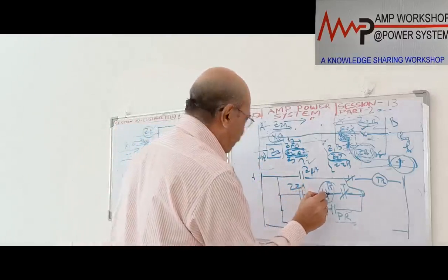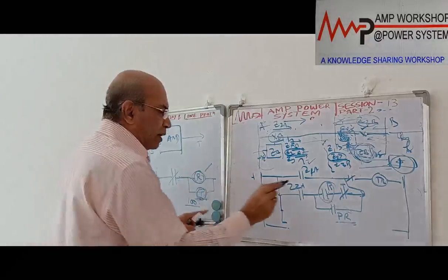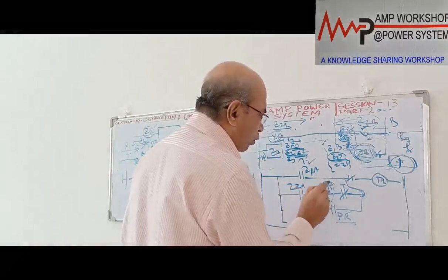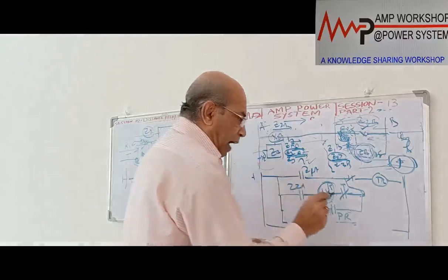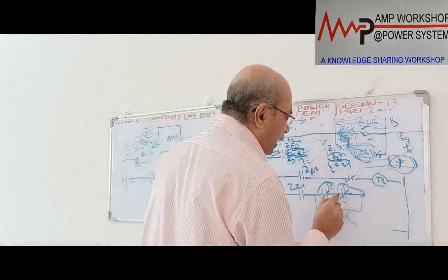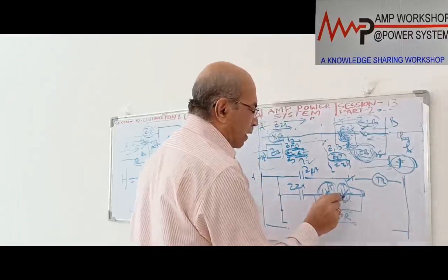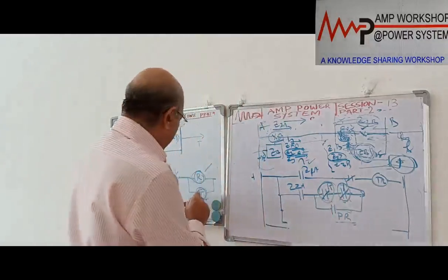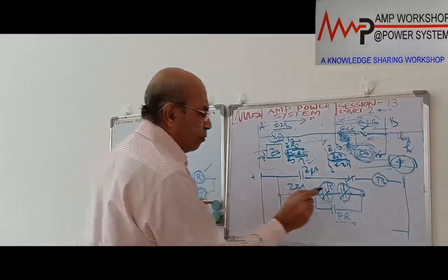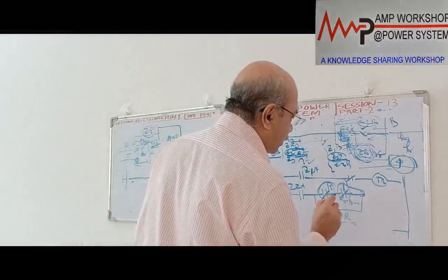Both the signals are off. In that case only this R relay will energize. So when this is picked up, it means both the signals are off, and after 150 milliseconds it will be open, because after that 150 milliseconds this timer will pick up. 150 or 100 milliseconds, the moment the timer picks up, it becomes NO. So this path will not be on.